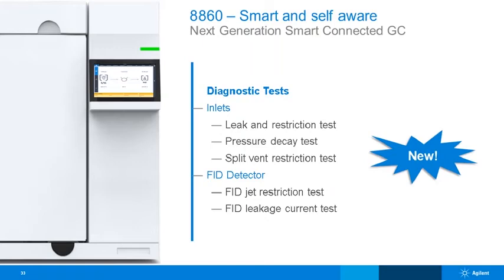So we have the diagnostic tests, so you've got inlet testing. This is really the key part of the whole GCs, to be fair, the new GCs. If you're using it, it would tell you whether you can do a leak and restriction test. So this means not only that as a result of putting a new column in there isn't a leak, but also that there's still flow. That's where the restriction test comes in. You've got a pressure decay test, and a split vent restriction test.